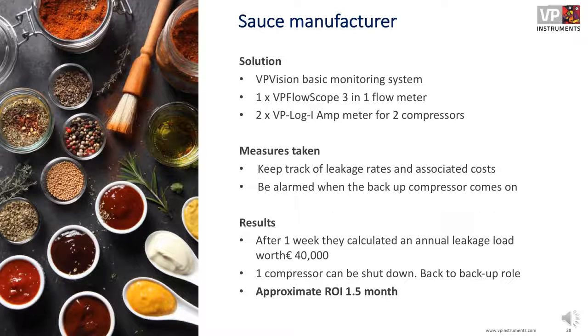We kept track of the leakage rates and the associated cost. We knew the kilowatt hour price, we knew how much the air cost, and we also set up an alarm through the VPVision system for when the backup compressor came on.